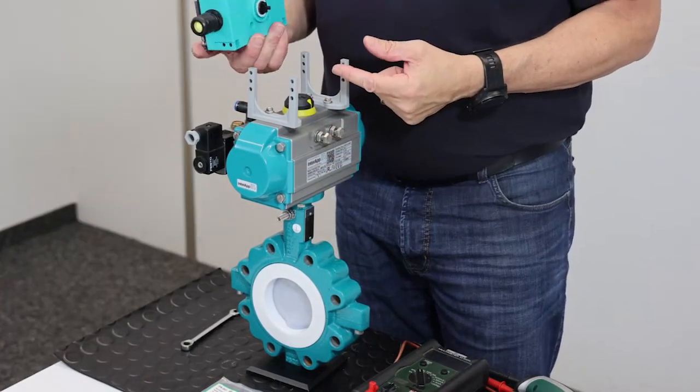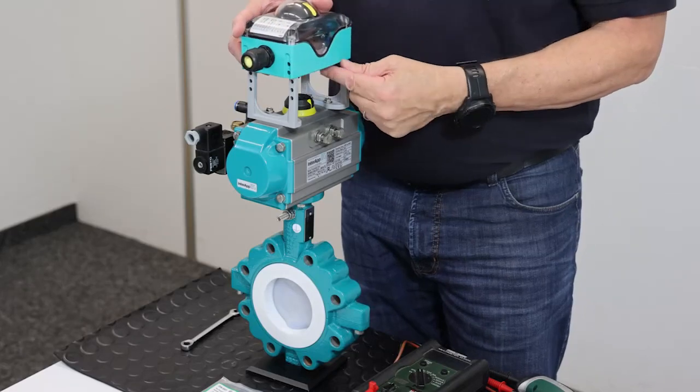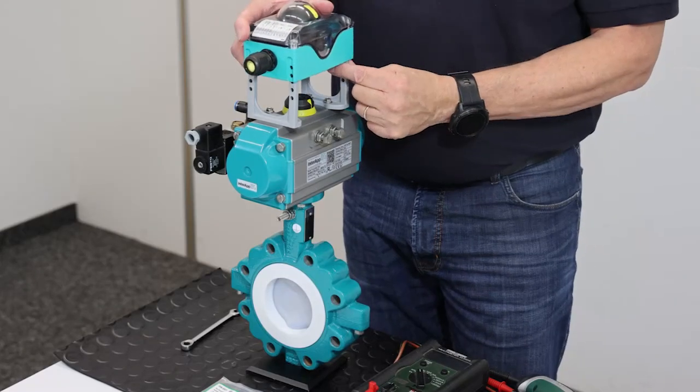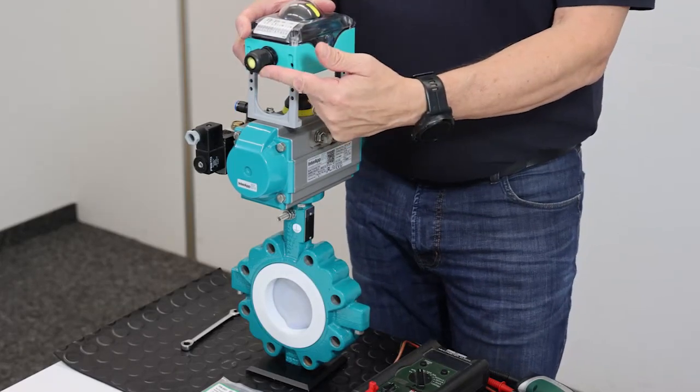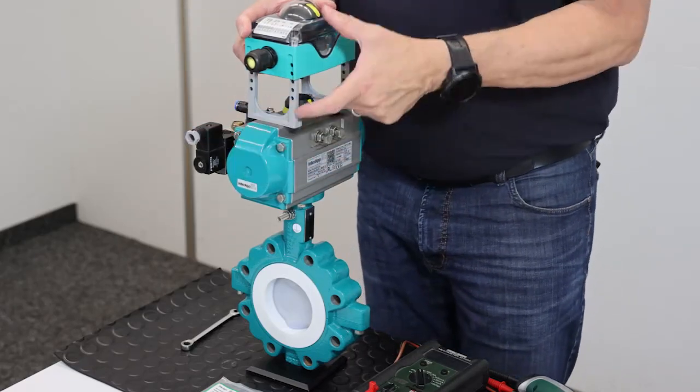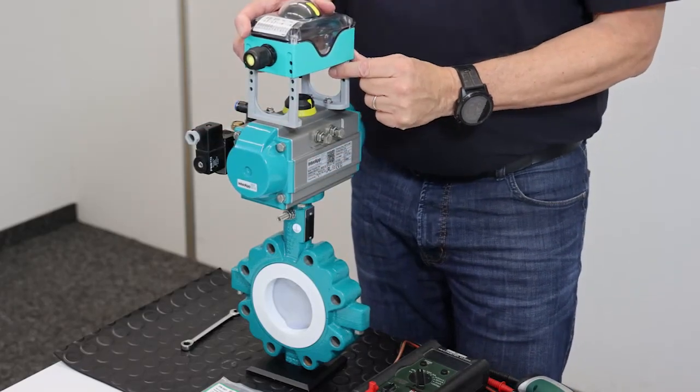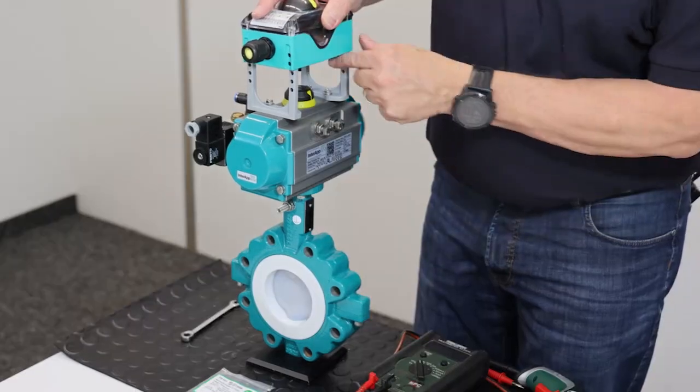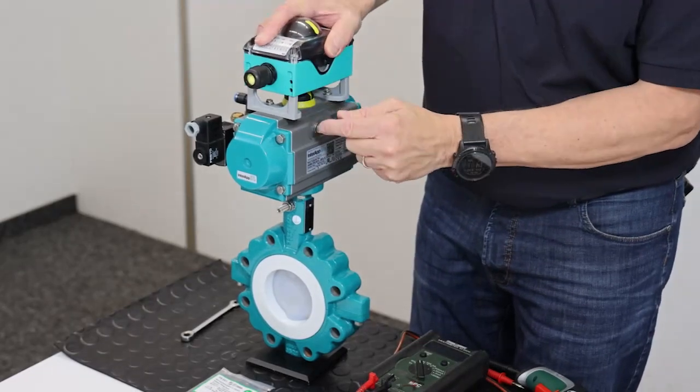The correct position of the limit switch box is that the cable entry of the limit switch box looks in the same direction as the cable entry of the solenoid valve. I mount now the box on top.